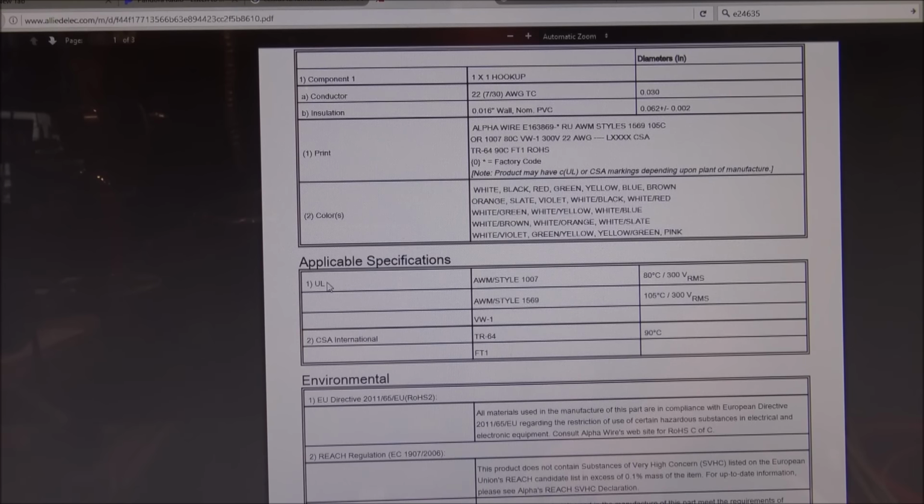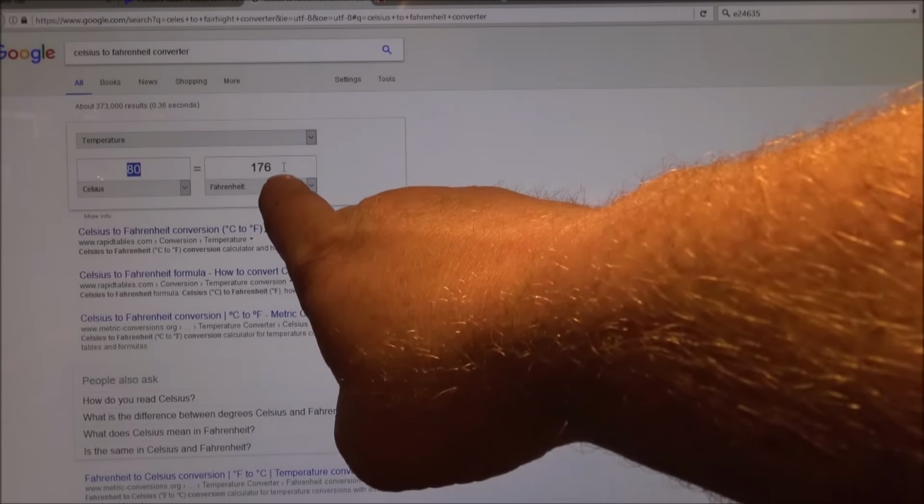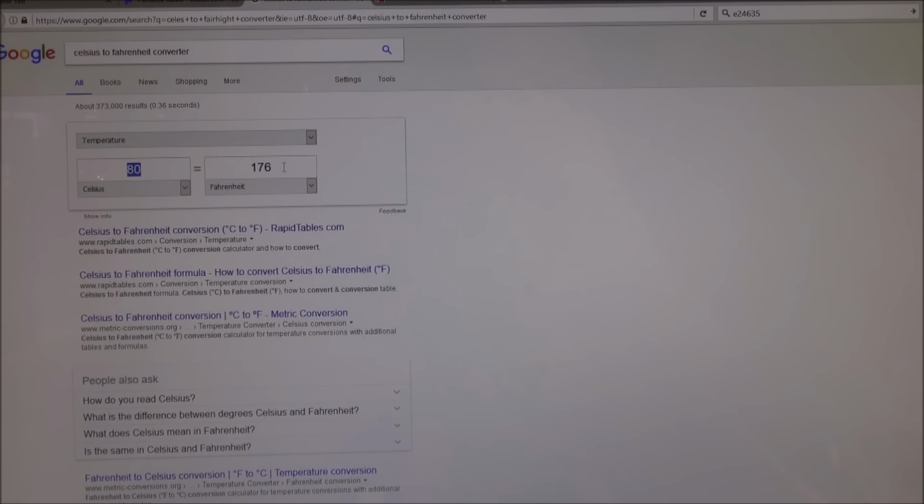So, now that we know about that, we can go over here and see the wire style: 80C at 300 volts, or 105 at 300 volts. When we do our Fahrenheit to Celsius conversion with Google, 80 Celsius works out to be 176 degrees. What they mean by that is this is its maximum usable temperature, where the insulation will maintain its ability to insulate itself from other wires or other voltages next to it, without the jacket becoming so soft that the wire can wander through the insulation, push it out of the way, or the insulation breaks down.